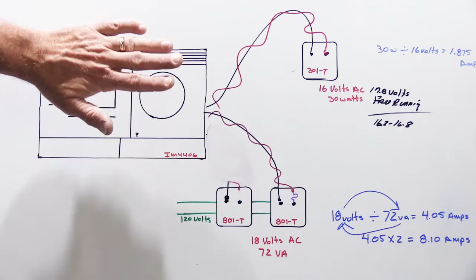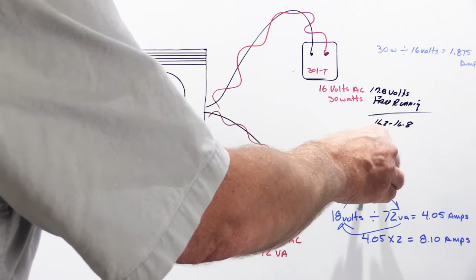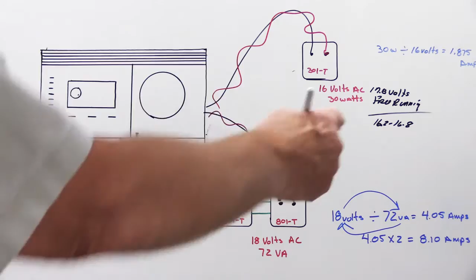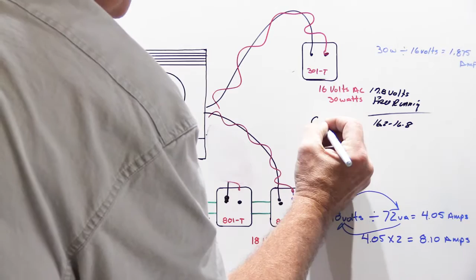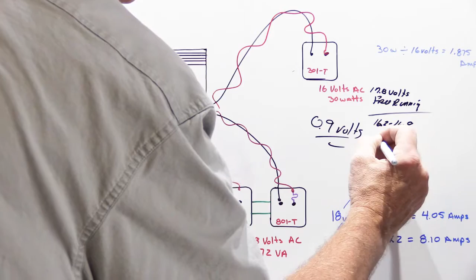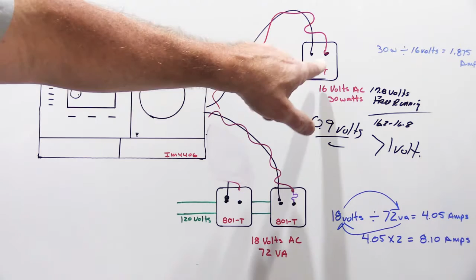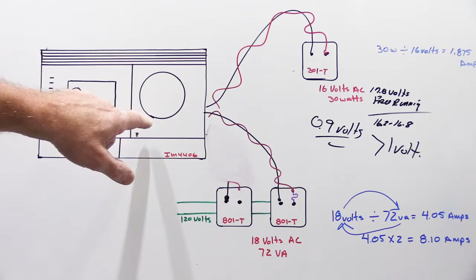If you do have a serious fault with your master station, when you power up the transformers again, what's going to happen to the voltage on the 301T is, instead of this 16.2 to 16.8 volt range that you would have if the master was okay, you're going to see some kind of voltage that could be as little as 0.9 volts, which is less than 1 volt. If you have less than 1 volt when this transformer is powered up, what that means is the master station has a failure or a fault in it, and it's drawing all of the power from the 301T that it can possibly supply, and more.